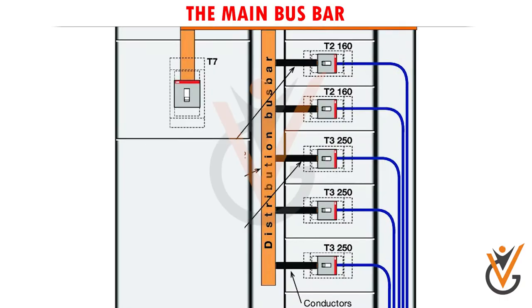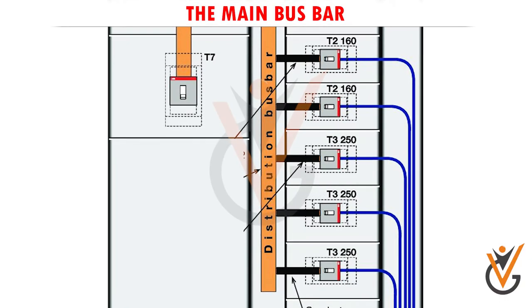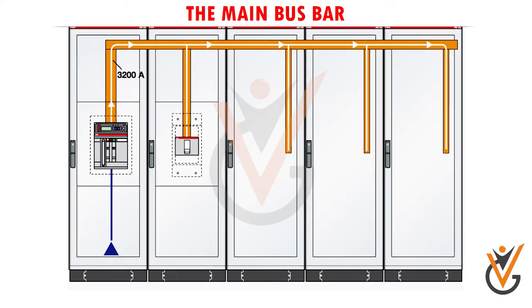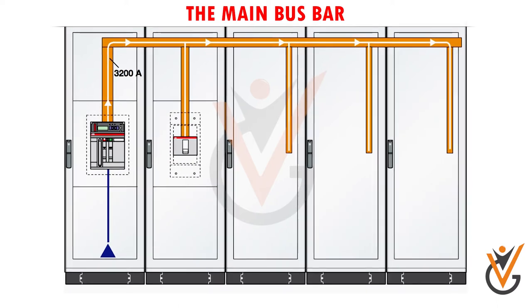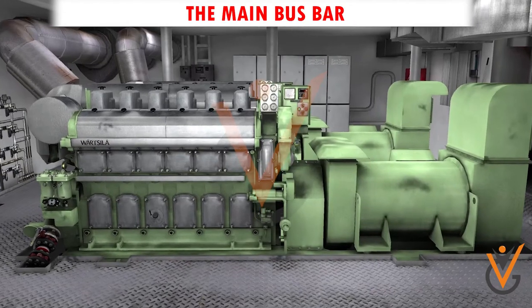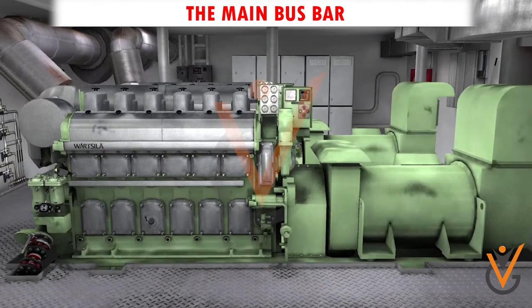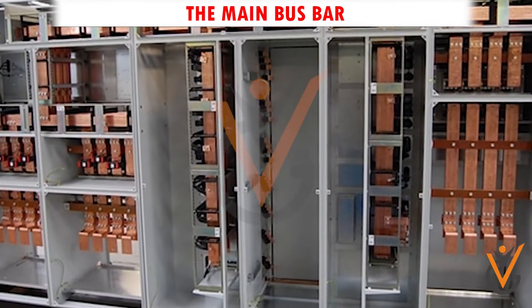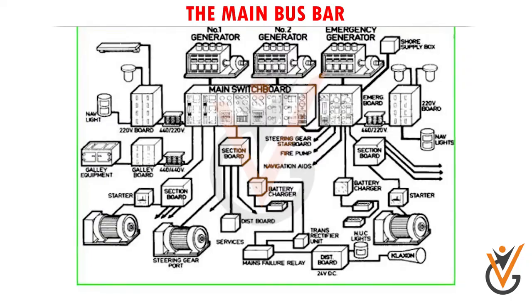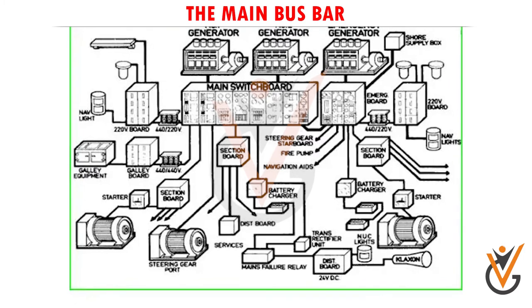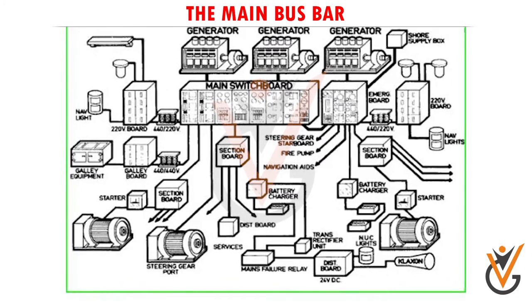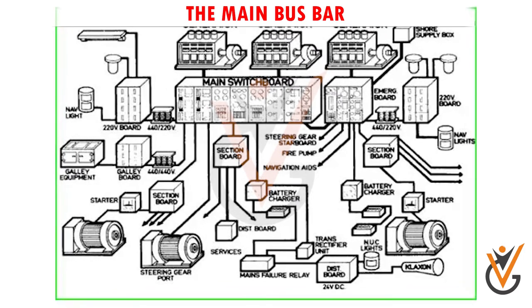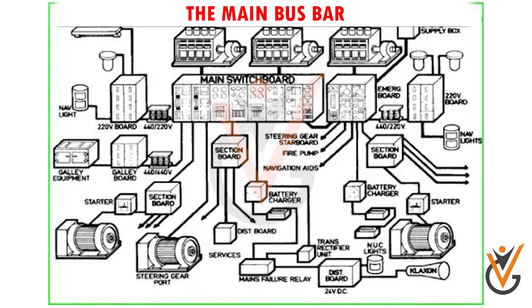The main switchboard is the main power distribution center of the ship, and the main bus bars are contained within it, feeding various shipboard auxiliaries. A ship may contain two or more generators connected to the main bus bar via circuit breakers. From the main bus bar, electrical power is supplied to various shipboard auxiliaries like pumps, blowers, compressors, etc.